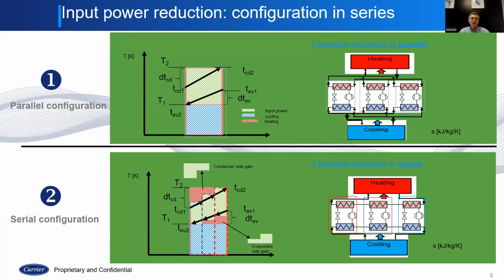So if in the top you have an air-cooled machine, this will be straight, so you won't gain much. You'll only have the part of the savings in the bottom. If you have water to water, and can afford to put both in series configuration, you can by nature have much higher efficiency than putting machines in parallel.